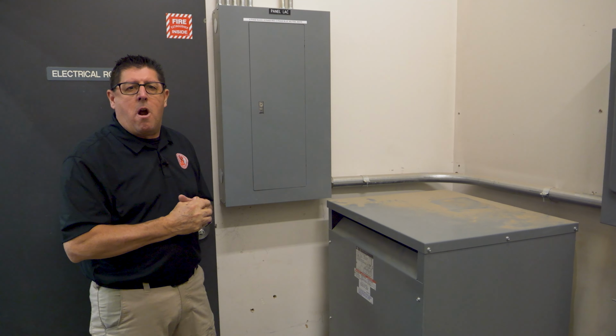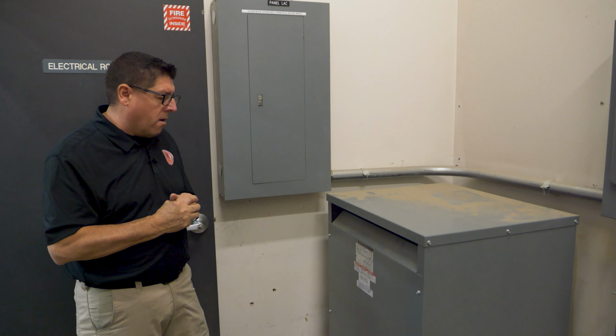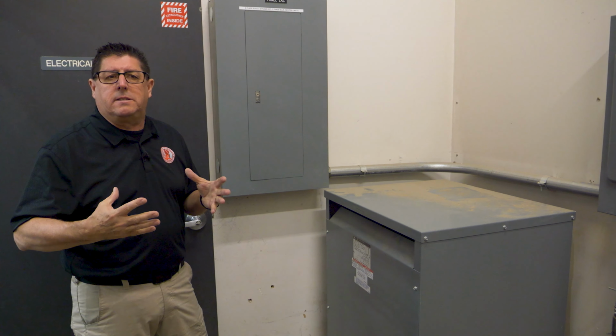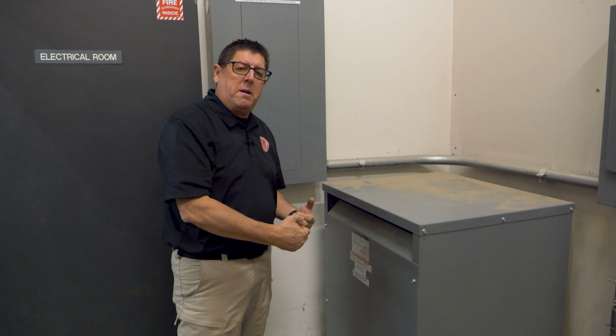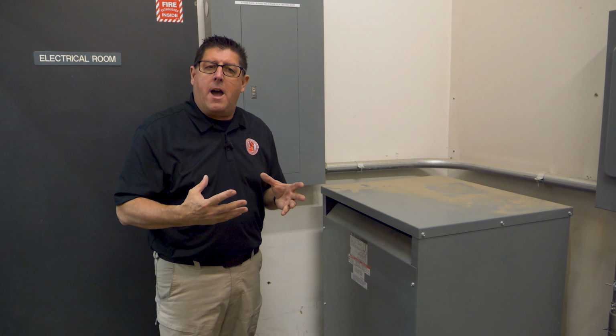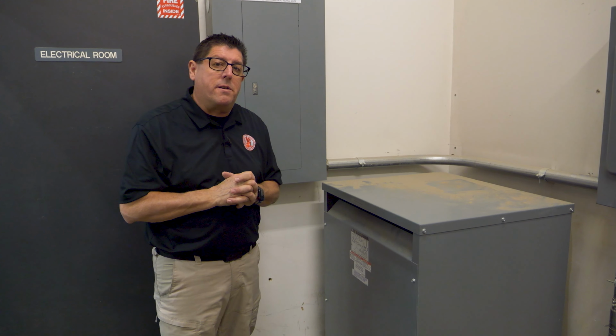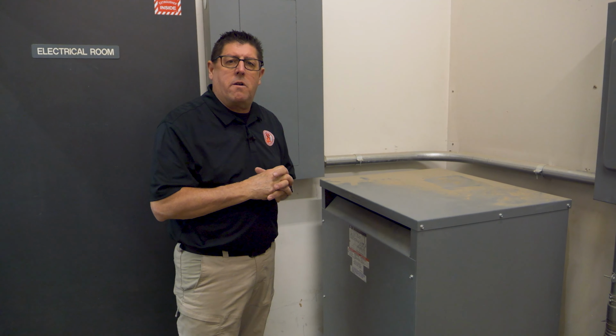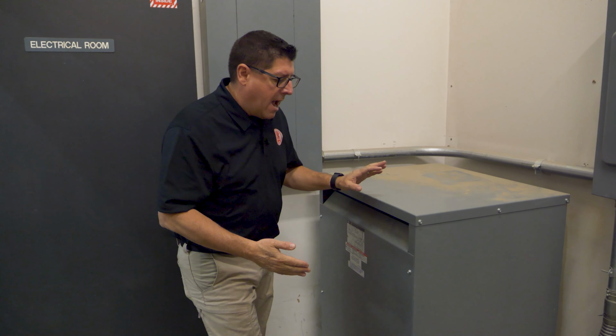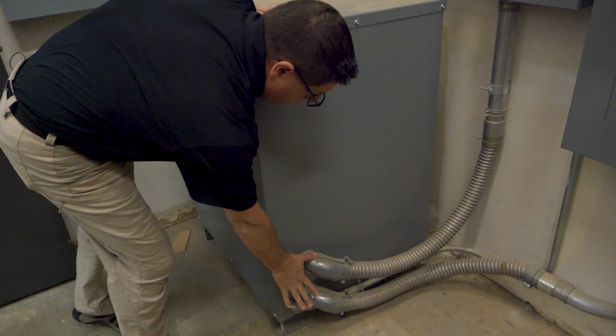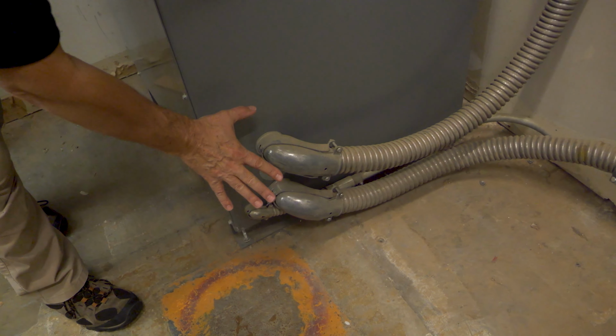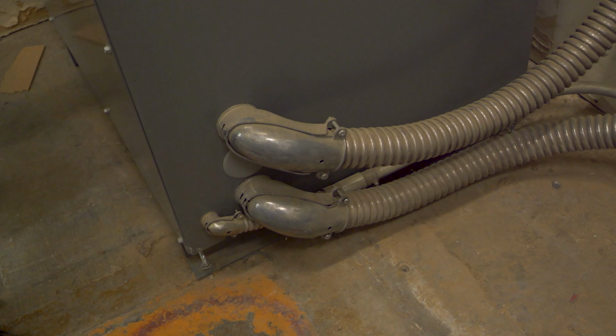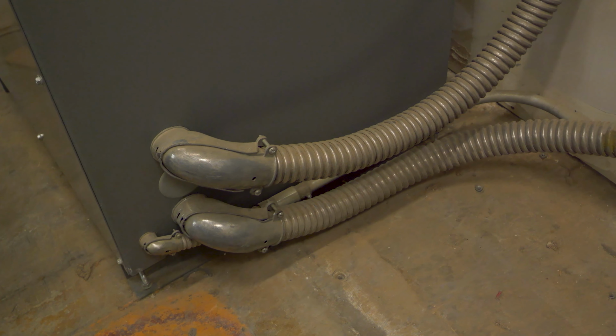This is an air-cooled transformer. Again, it's making a lot of buzzing sound. It does produce some heat, but what I'm identifying next is our conduit. Our conduit needs to enter and exit the transformer at the bottom third of the unit. It's at the bottom third of the unit because of the heat.